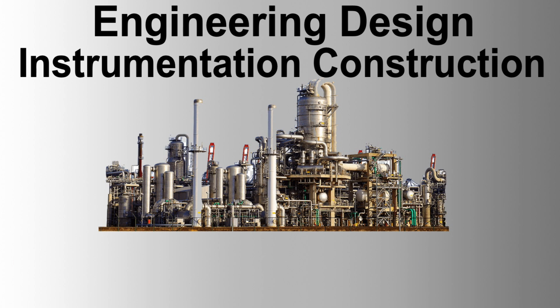After removal of the packing, the consoles and system cabinets shall be moved immediately into the control room. The packing material shall be transported to a safe location for eventual disposal. The consoles and system cabinets shall be handled very carefully to avoid undue stresses to the metalwork or damage to the surface finish and the instruments, etc. The handling of consoles and cabinets may be facilitated by using trolleys or skids specifically designed for the job.